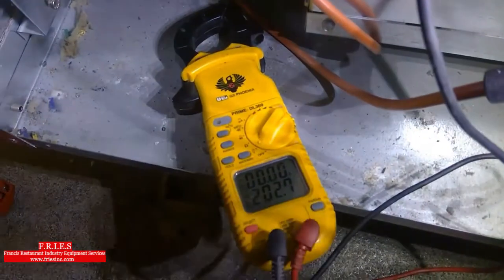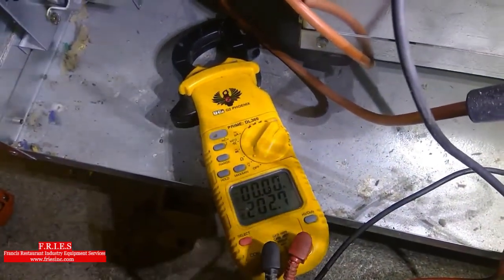So we've lost our voltage here at the thermostat. So I'm going to test across it to confirm. We're going to test potential difference here. My blower motor is running. And we have 202 across, which tells me this thermostat high limit is in the open position.